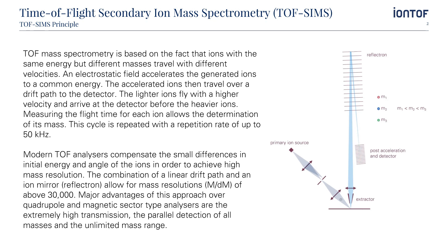Modern TOF analyzers compensate for small differences in initial energy and angle of the ions in order to achieve high mass resolution. The combination of a linear drift path and an ion mirror — reflectron — allows for resolutions of up to 30,000. Major advantages of this approach over quadrupole and magnetic sector type analyzers are the extremely high transmission, the parallel detection of all masses, and the unlimited mass range.